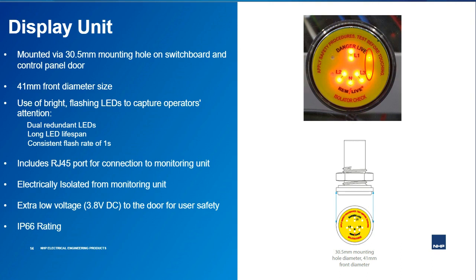As mentioned in the previous slide, the two banks of LEDs located on opposite ends of the display unit, and I've highlighted their positions on the image on the slide as well, will always indicate if voltage between any two connected conductors is greater than the minimum specified voltage level that the unit can monitor. When set to flashing mode on the monitoring unit, which is what we looked at in the previous slide, the LEDs located on the sides maintain a consistent 1-second flash rate if live voltage is detected.